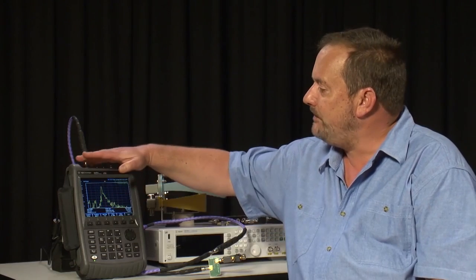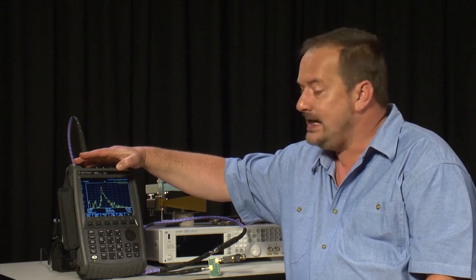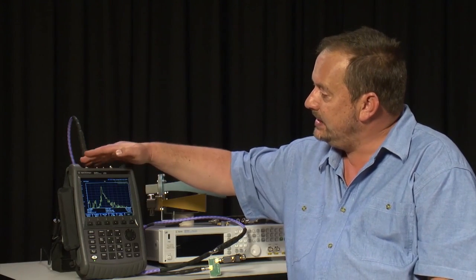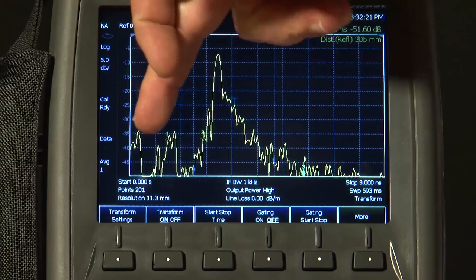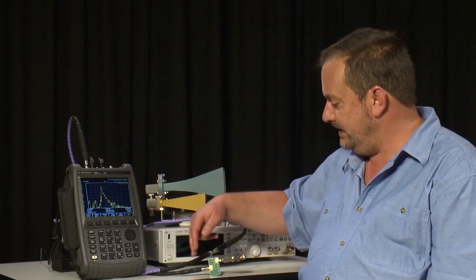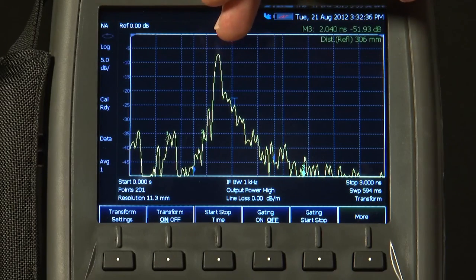Now 0 seconds is our time reference and that corresponds exactly with the calibration plane when we calibrated. In this instance we are using the CalReady that came with the FieldFox, so we know that 0 seconds is this point here. And as we move along the trace, we are moving through the measurement system until eventually we reach the filter, which is this large response here in the middle of the display.